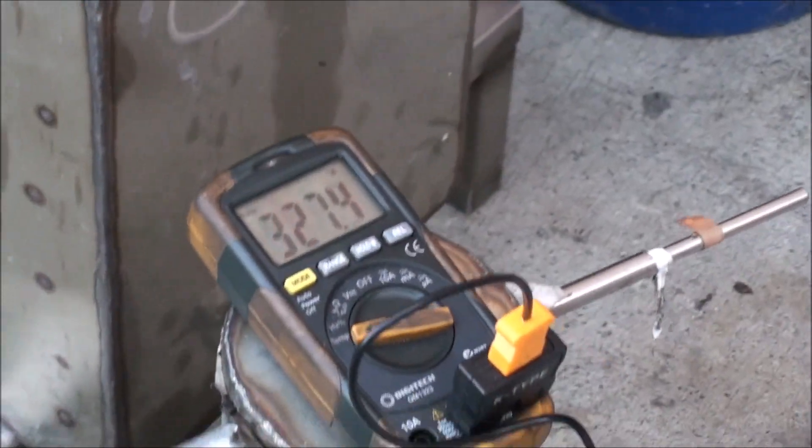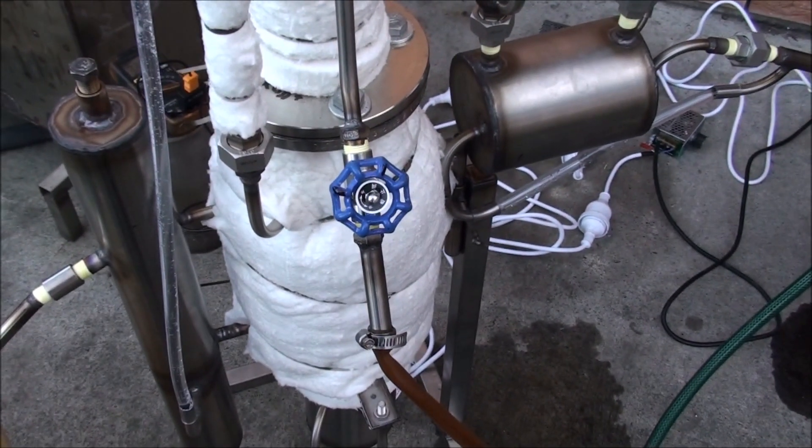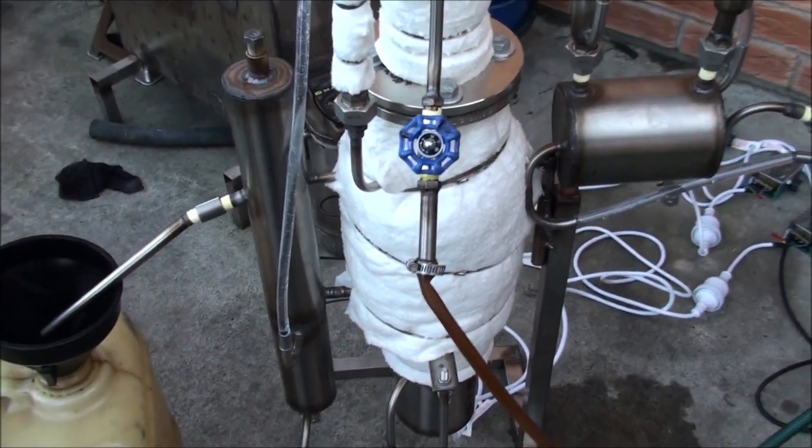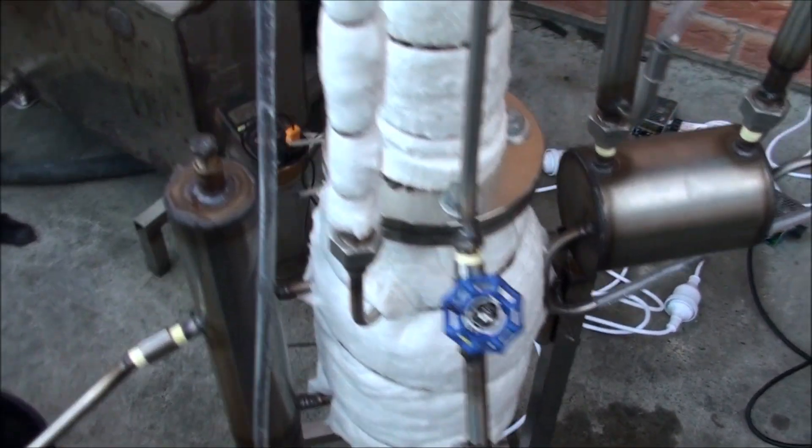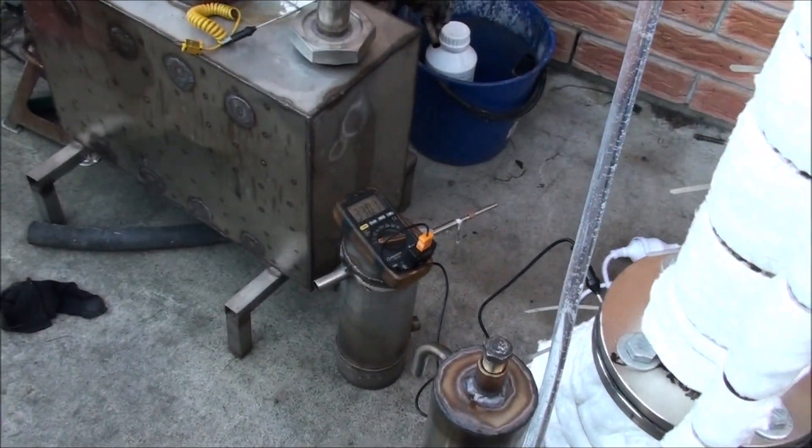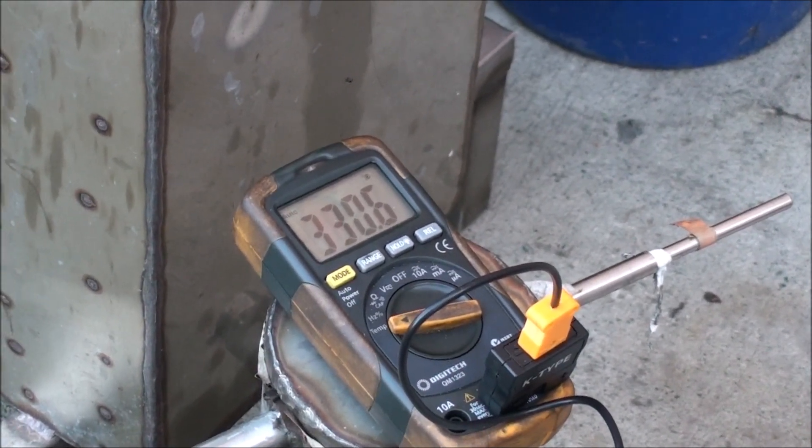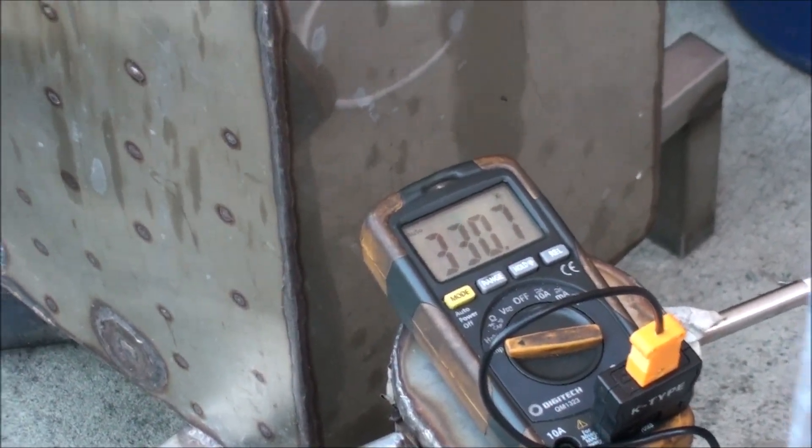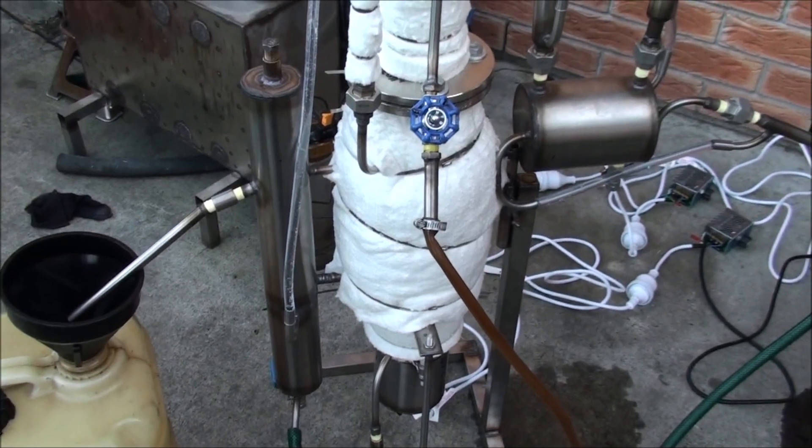And it's quite difficult to control the temperature completely with the supply mode, with the speed flow. So just adjust it, let it run away a little bit. And now manually switching on and off one string of the elements once it's reaching the certain temperature, 340 degrees. But it's not ideal conditions. I'm just testing this unit for the customer.